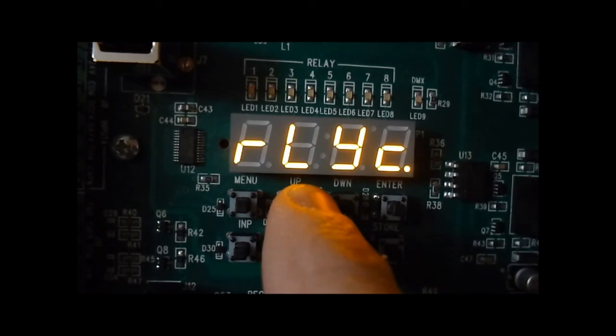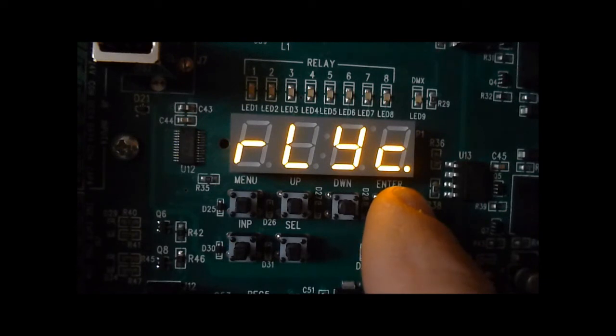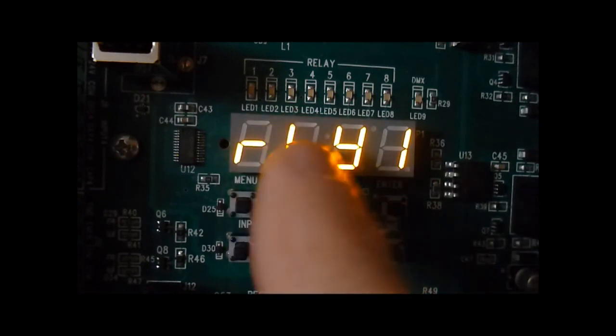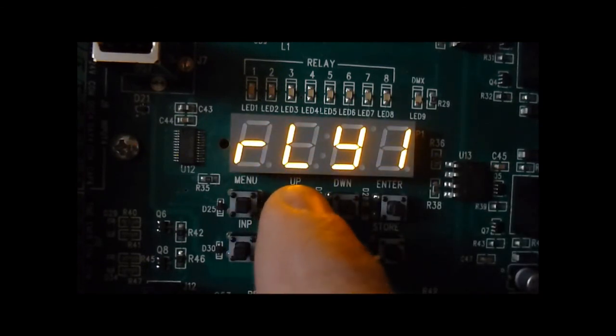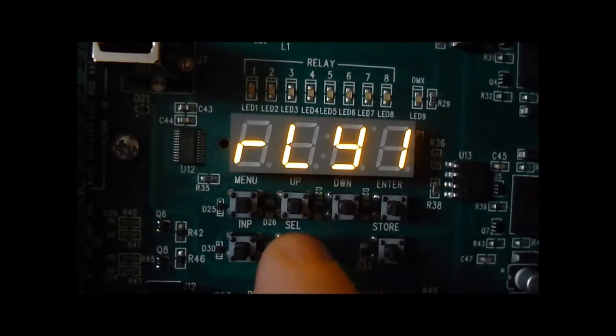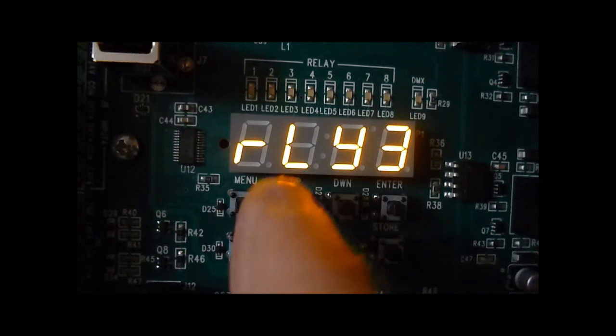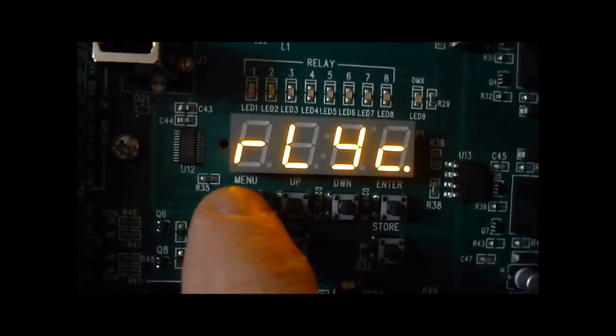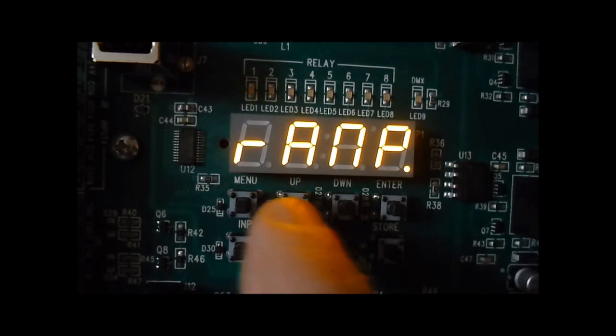The next menu item is relay control. This is a single zone at a time relay test, temporary. Press enter and we can scroll through all the zones - four zones for this unit. Press the select button and the relay goes on, press it again and the relay will go off. Scroll to the next relay. This will also put the zero to ten volt output at 100%.